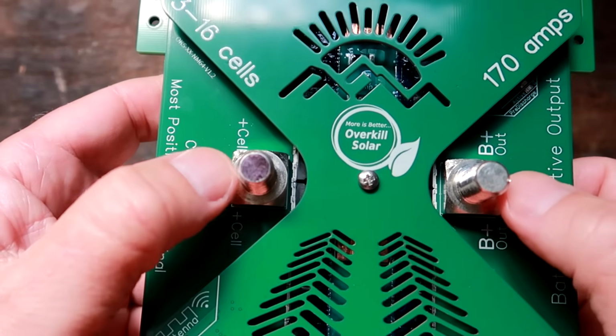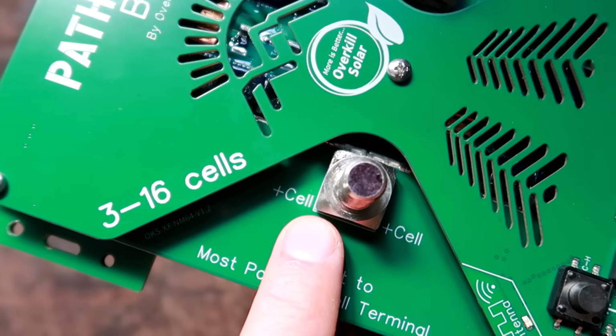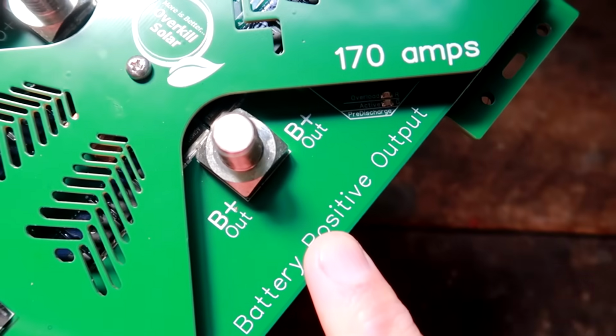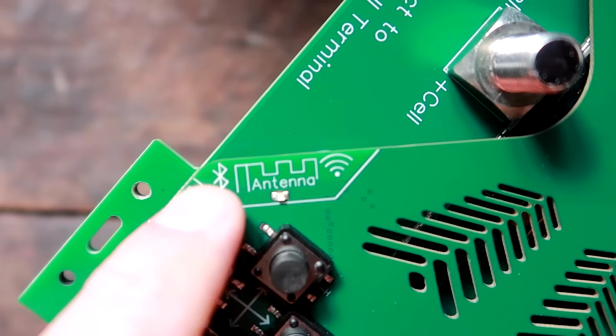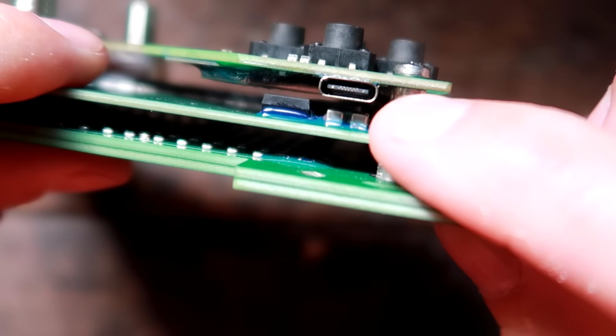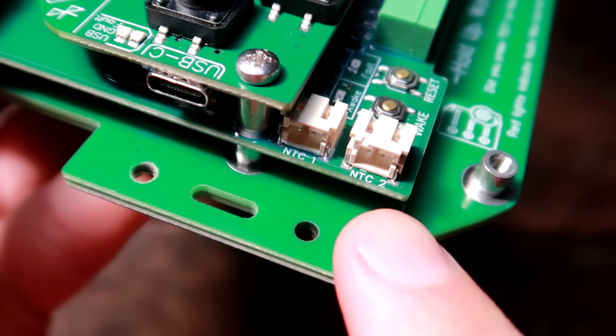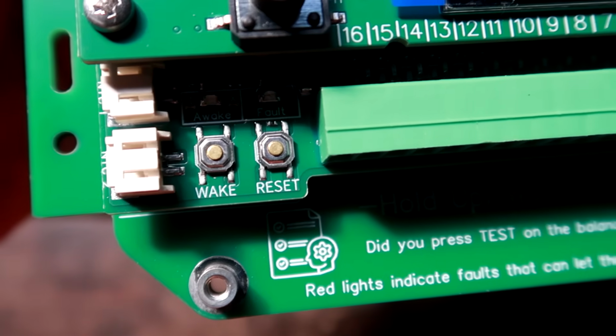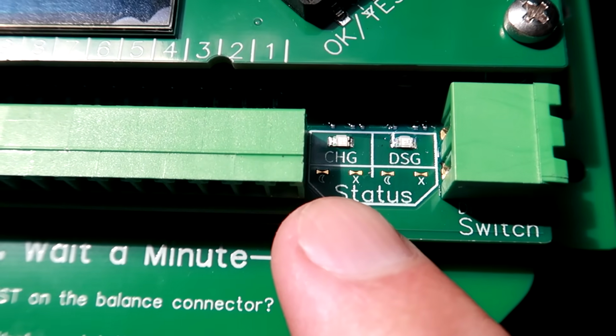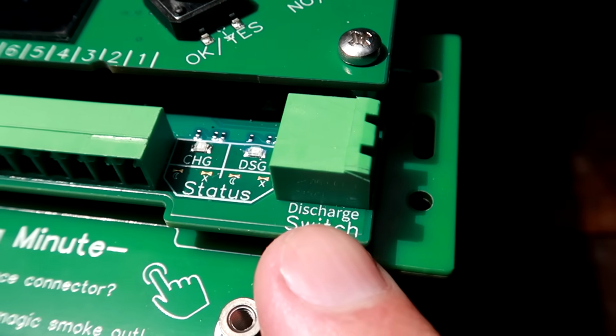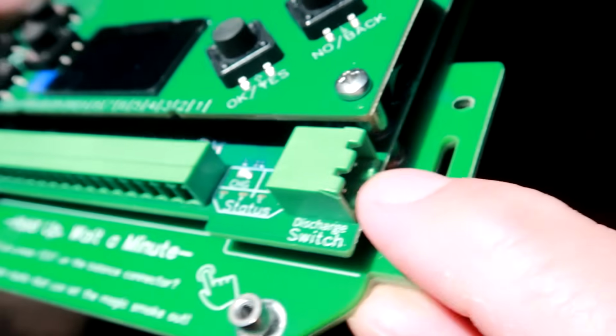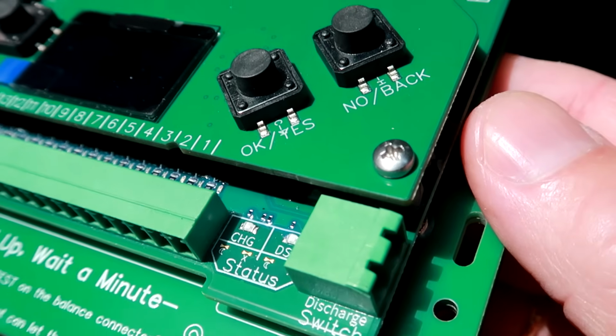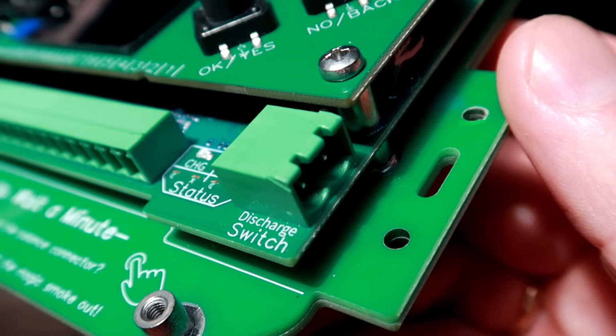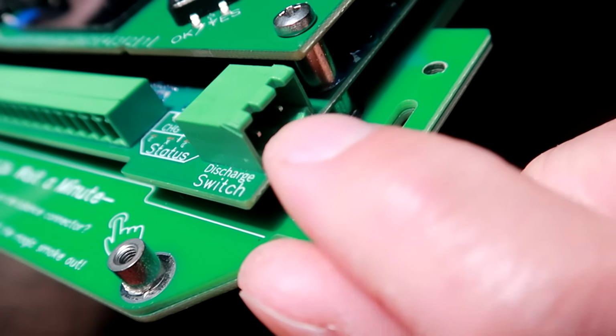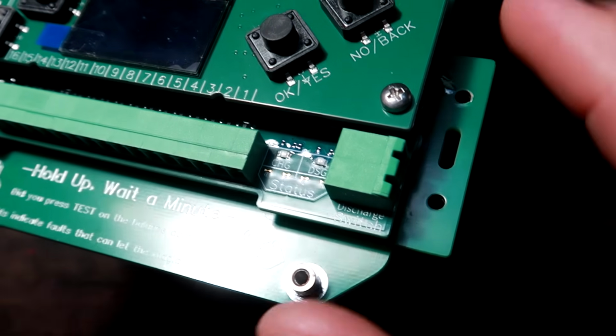So obviously we have the 2 M10 terminal studs left and right. One connects to your battery, most positive, and the other one connects to your load and chargers. We've got connections for Bluetooth and Wi-Fi, as well as a USB-C connector, 2 connectors for temperature sensors, a wake and reset button, the connector for the balance cables. On this side we've got 2 LEDs for charging and discharging, and a discharge switch. If you connect these 2 pins, discharge will actually turn off. This is especially very useful and handy if you frequently connect inverters to the BMS. You just close the switch between these 2 contacts, discharge is off, you connect your inverter and turn the BMS back on. More about this feature later.